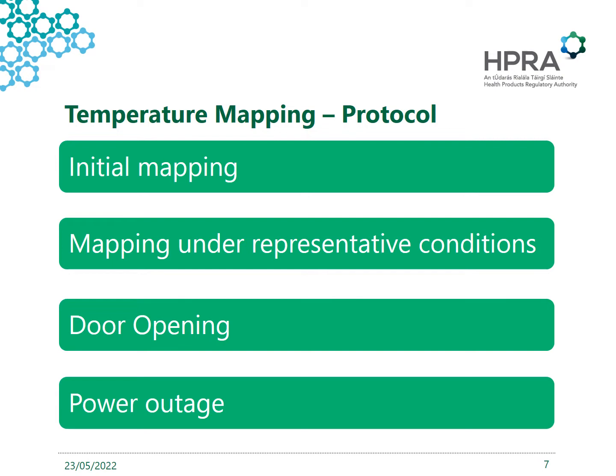The same goes for door opening: consideration should be given to both the frequency and duration of door opening based on the envisaged activities. For example, how many consignments are expected to be received in a given week, month, etc., and the same goes for goods out - how many consignments will be sent in a week, month, etc. It's important to justify the frequency of door opening within the study or the protocol.